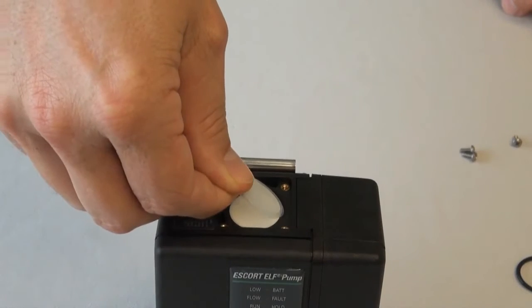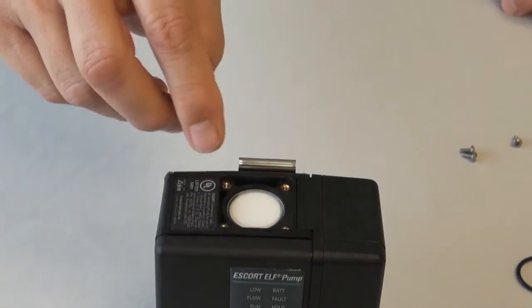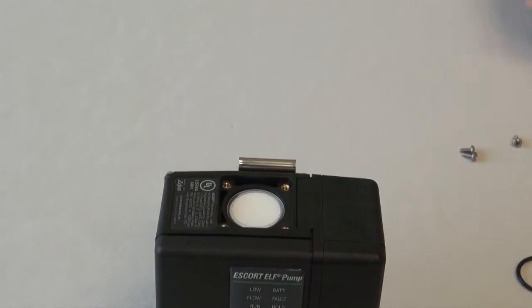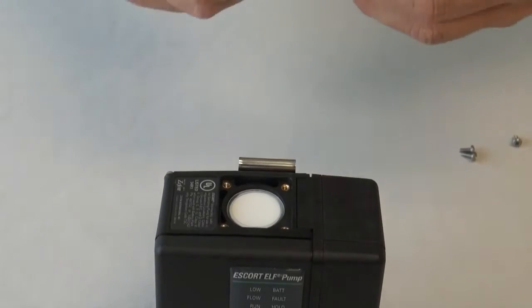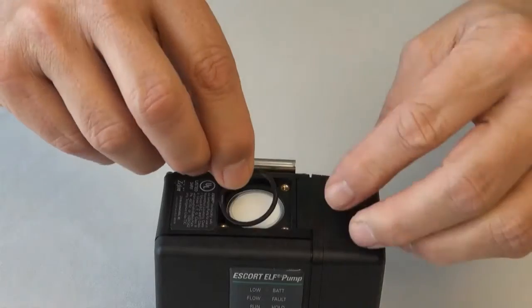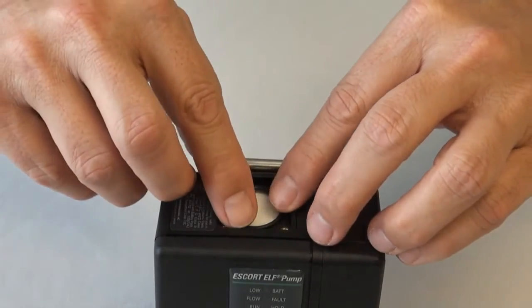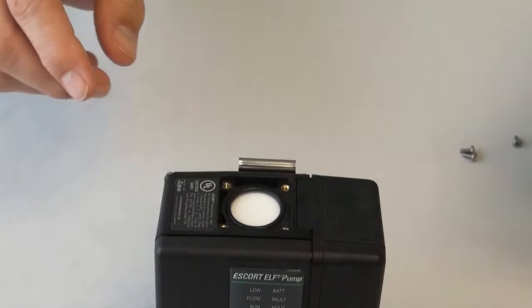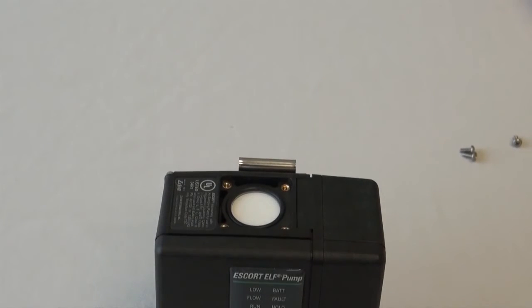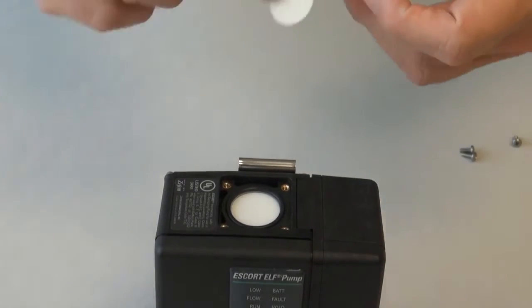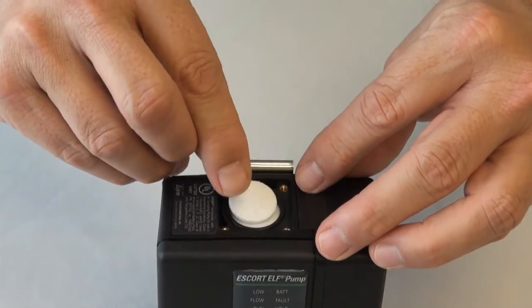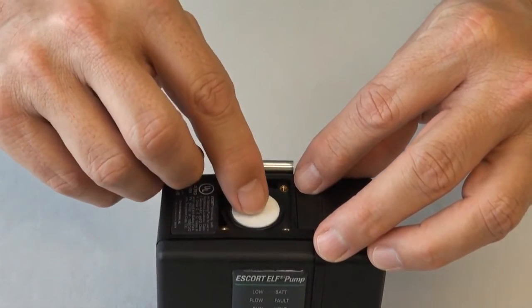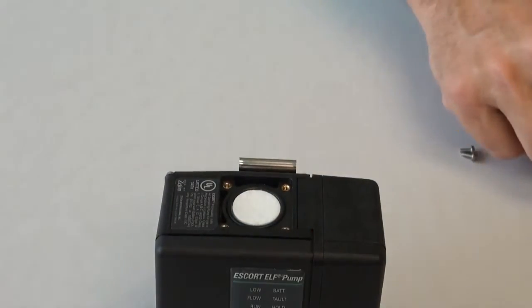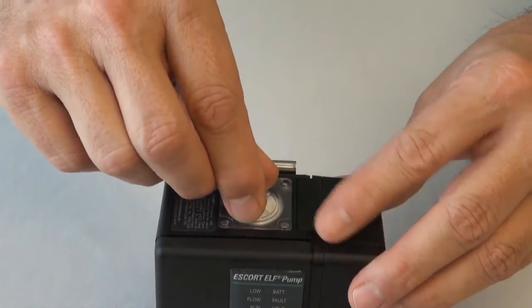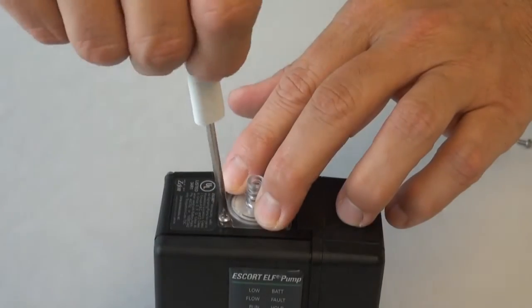Carefully place the water stop filter over the frit and into the proper position. Make sure that you visually inspect the O-ring for any damage. If the O-ring is good or a new one is used, set it into position. Now you can replace the inlet dust filter. Before fastening the inlet dust cover, inspect it to confirm that it is not cracked. Now carefully tighten the 4 screws so that the O-ring stays in place and doesn't get pinched.